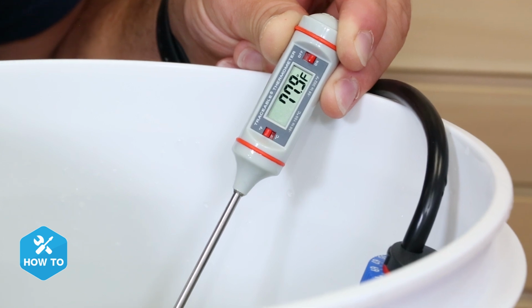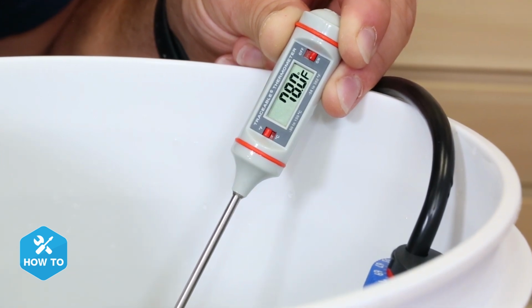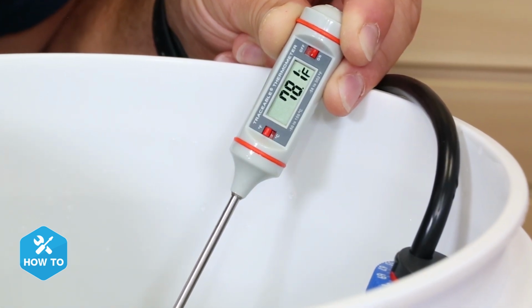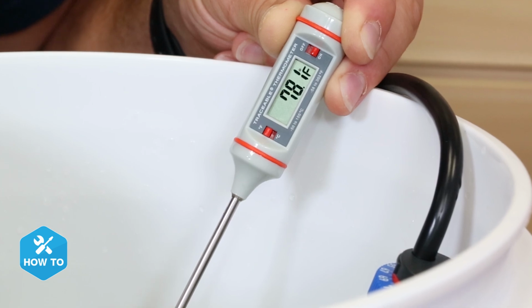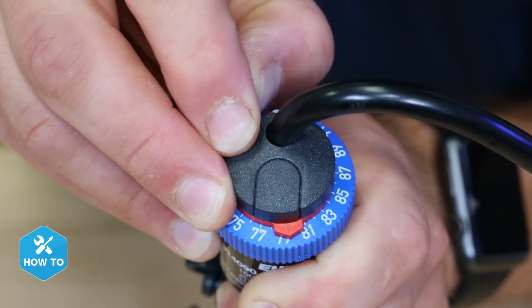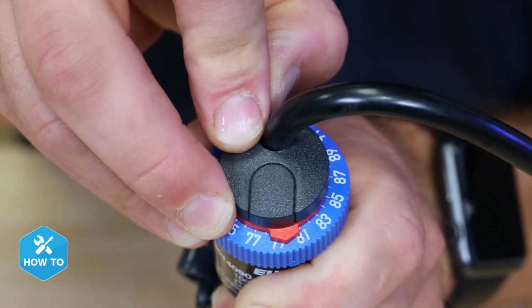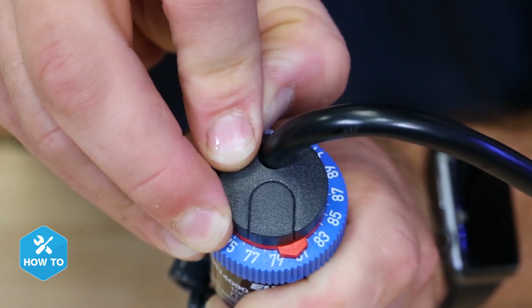With my thermometers in a bucket of water, I can watch them until they stabilize at a single temperature and then adjust the red calibration ring to that temp. For example, if my heater's set at 78 degrees but my thermometers stabilize at 81 degrees, I can simply move the red pointer until it lines up with the 81 mark on the blue adjustment ring.